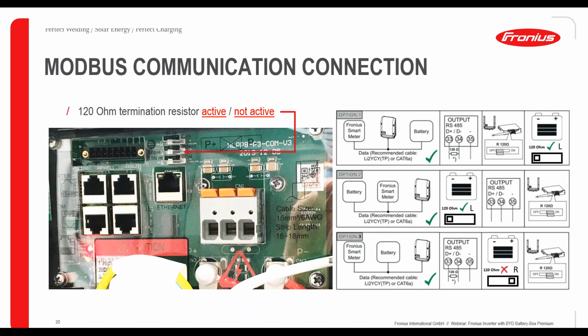So first of all, the Fronius smart meter is on one side of this communication path, and the battery is on the other side. That means that the Fronius inverter is in the middle of this communication path, and therefore the Fronius inverter has to have a deactivated 120 ohm resistor, and the battery and the Fronius smart meter have to activate the 120 ohm resistor to terminate this communication. So in this case, you can set a 120 ohm resistor on the Fronius smart meter. This is in the delivery of the smart meter. You can set it between D plus and D minus. And of course, with the battery box, you just set the dip switch to active. On the other side, on the inverter, you just set the dip switch on the data manager plug to off, and therefore the 120 ohms are deactivated.